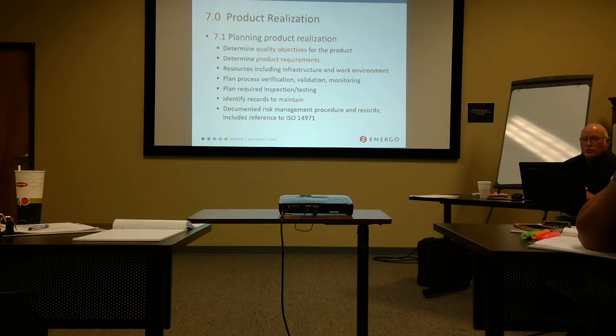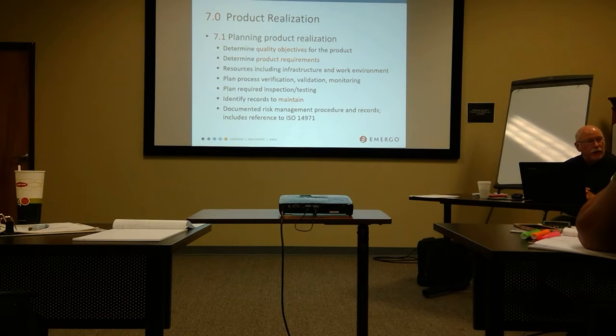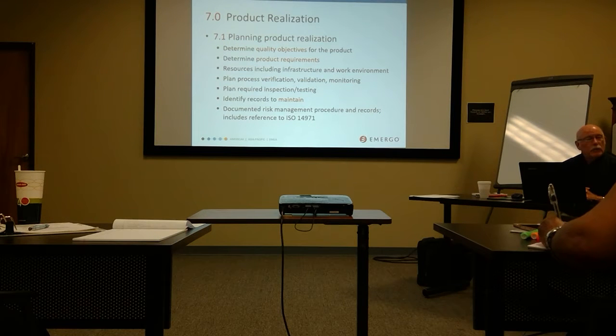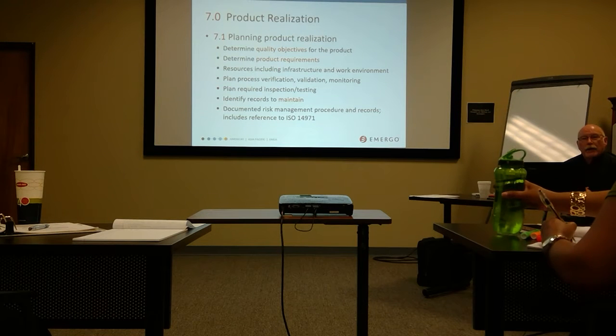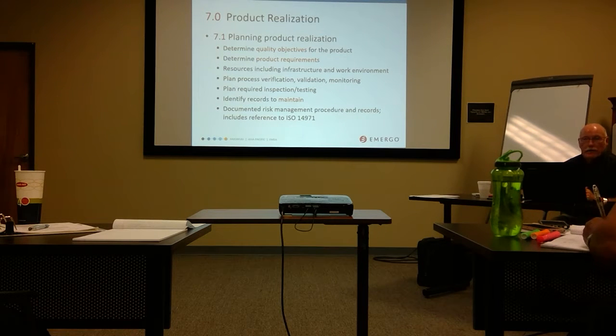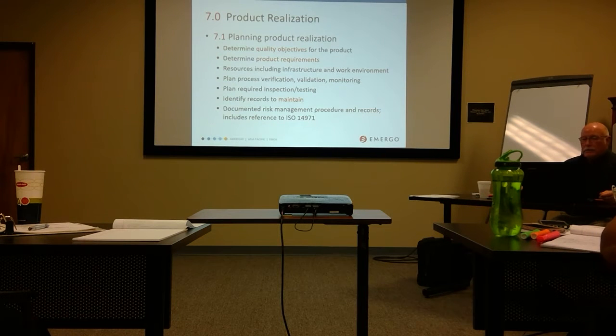Documented risk management to standard — there's a specific element now in ISO 13485 that requires you to reference the risk management standard, which is ISO 14971, which we'll talk a lot more about shortly. Realize that there are two versions of that standard. If you manufacture for distribution in the United States and Europe, both of them apply. One does not supersede the other. They both apply, and we'll go into detail on that in a bit.